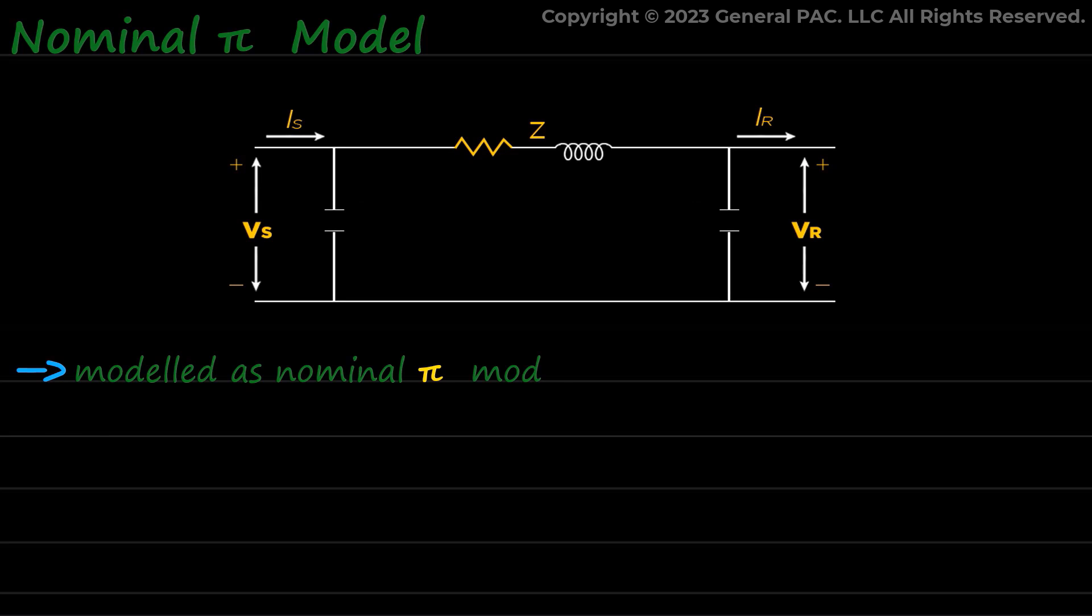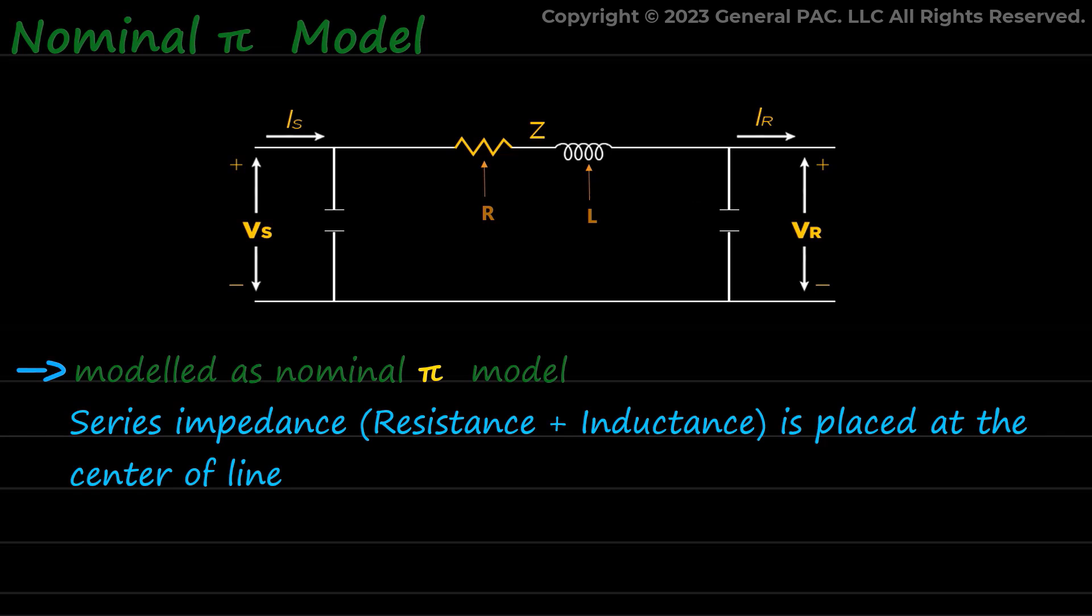Nominal pi model. As we have previously mentioned, the medium transmission line can be modeled as nominal pi model in which the series impedance (resistance plus inductance) is placed at the center of line, whereas one half of the capacitance between phase and neutral is lumped at each end of line, which is shown as the shunt admittance Y in the diagram.